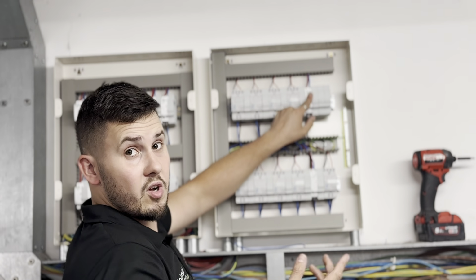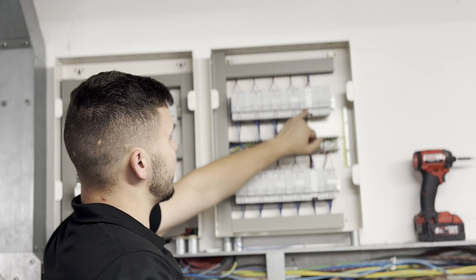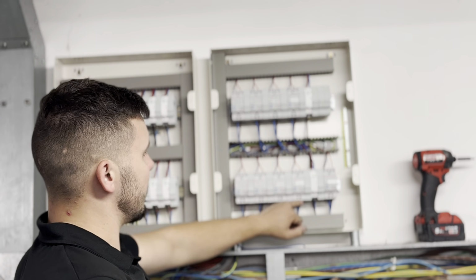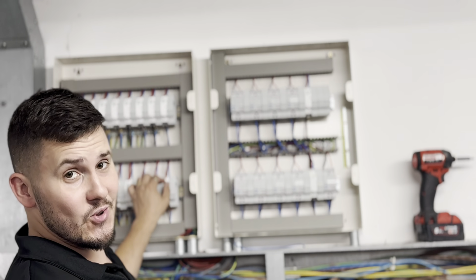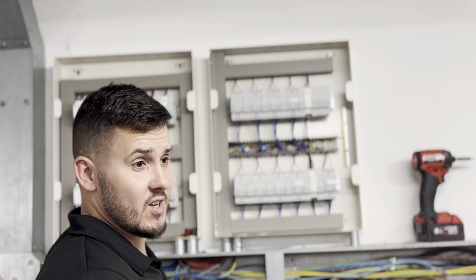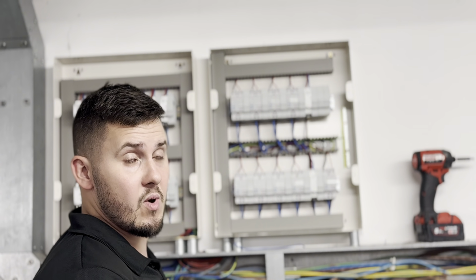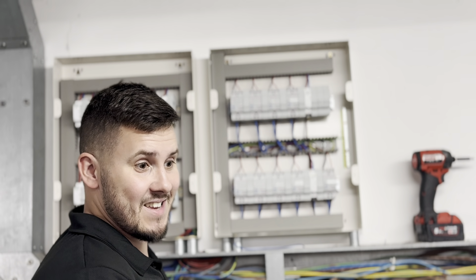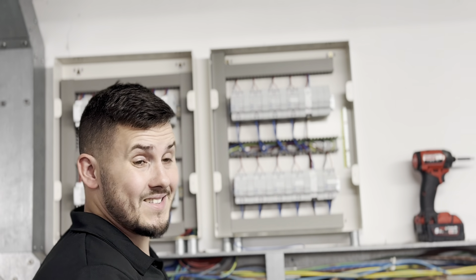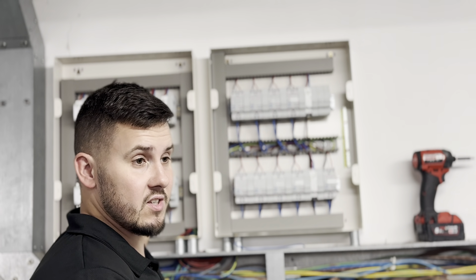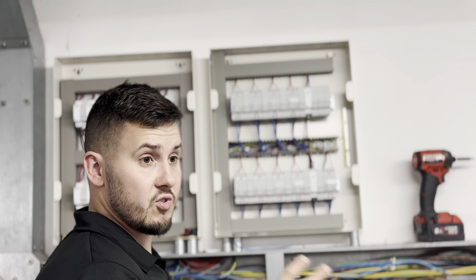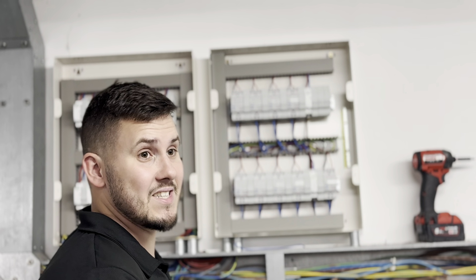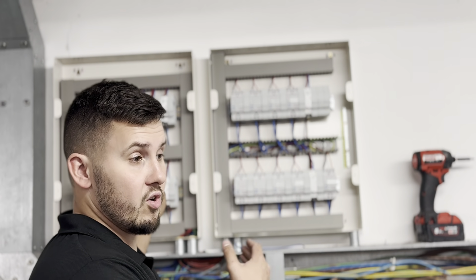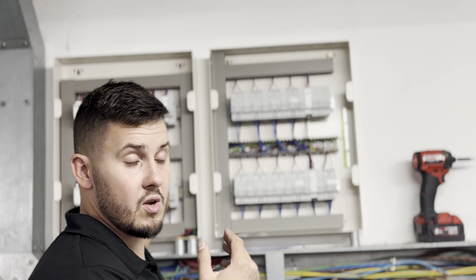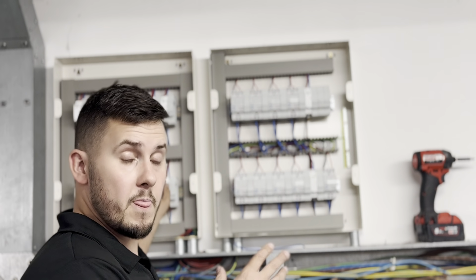Our primary control circuit literally turns on those 2 contactors, which in turn turns on all 8 of our transformers, each of which turn on 2 contactors. It's a really rubbish way of having to do it, but it's the only way we can make it work with materials we could get easily in a really short period of time. Ideally we'd have had a decent Schneider or Wago transformer, a 24-volt transformer with a decent volt-amp output that could turn on and off the coils of all these contactors, but realistically we couldn't get that in time, so we've opted to do this.